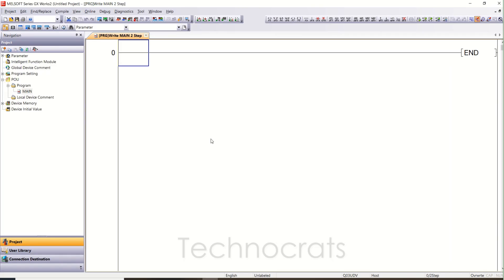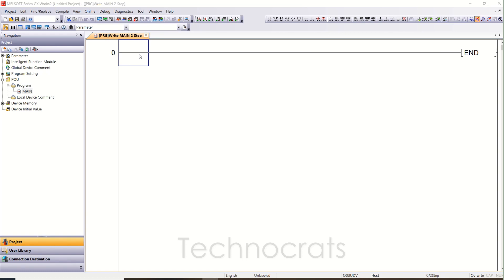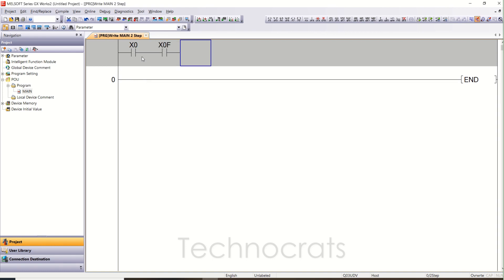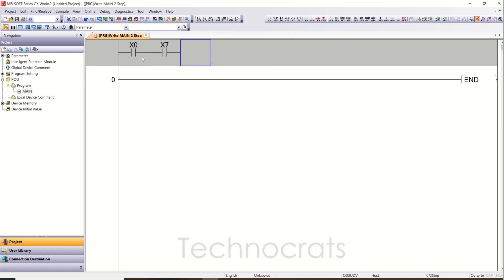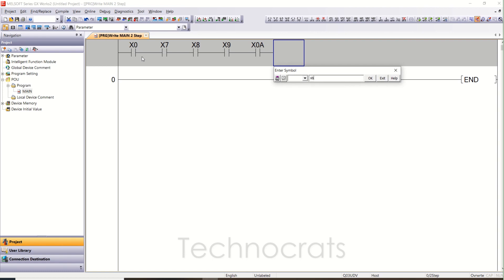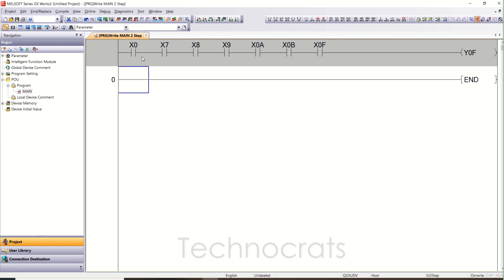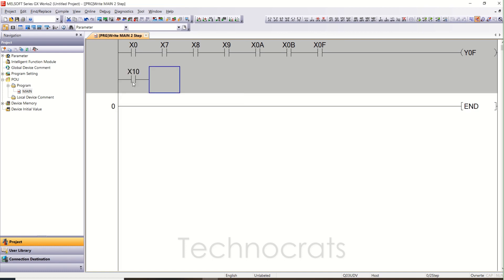Now GXworks2 is open. For Q series PLC, inputs start from X0 and go till XF — that is a total of 16 bits. So that will include X0 to X7, then X8, X9, XA, XB, XC, XD, XE, and XF. After X0F it will jump to X10 — that is the next group.